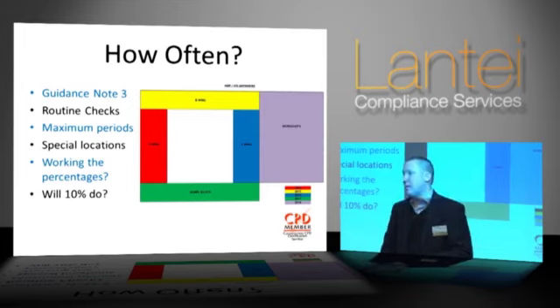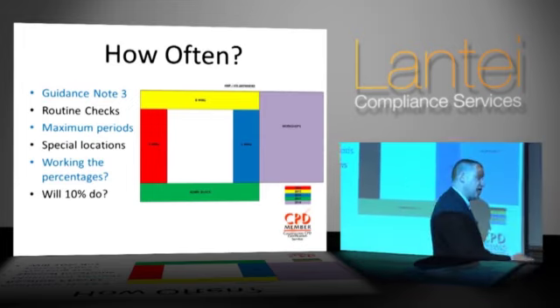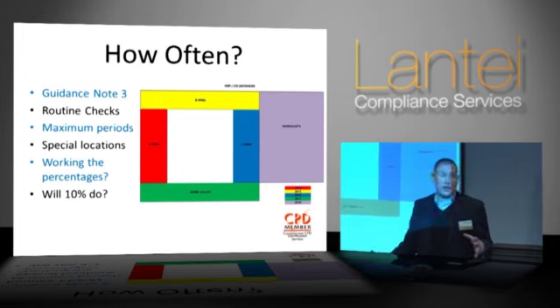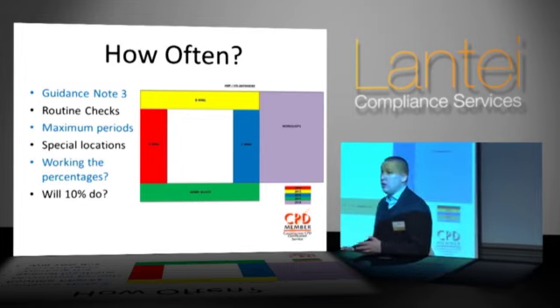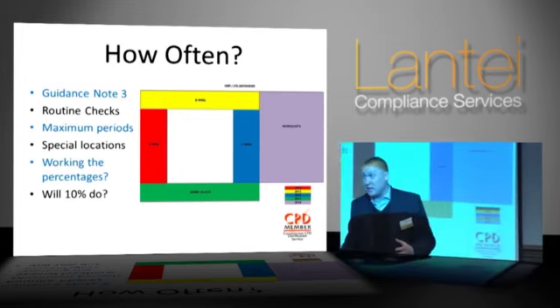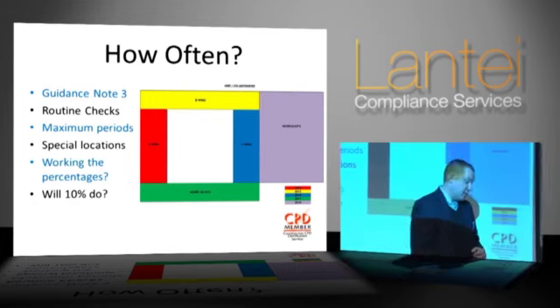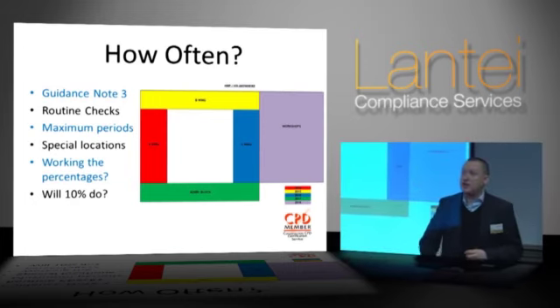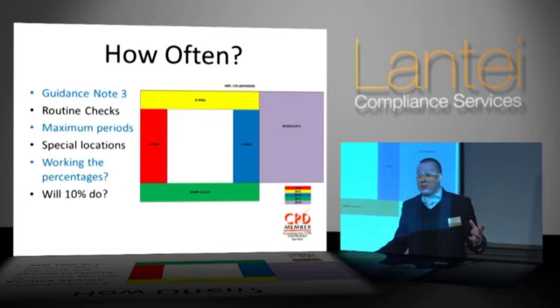The reason an engineer might put 3 years is because they've seen deterioration in the electrical installation. They're concerned it won't last another 5 years, or that more regular checks are needed because its condition isn't what it was when first installed.